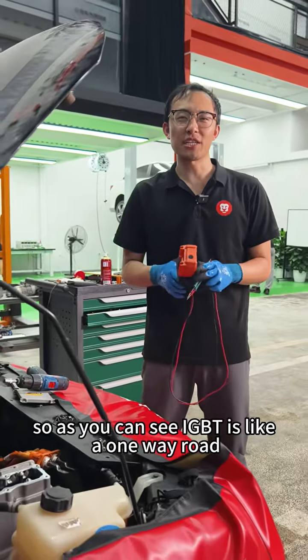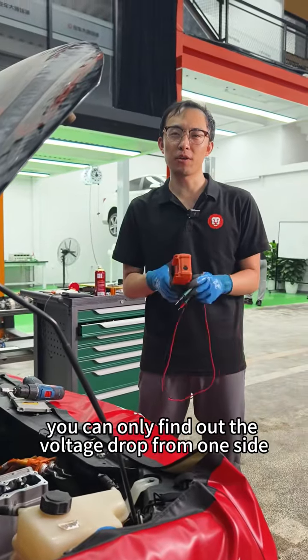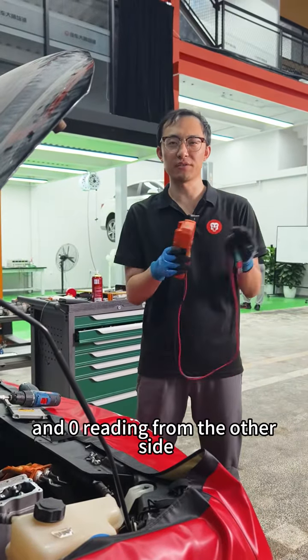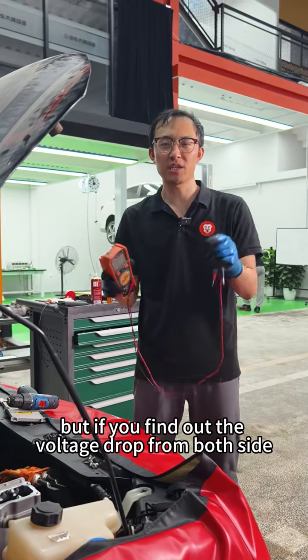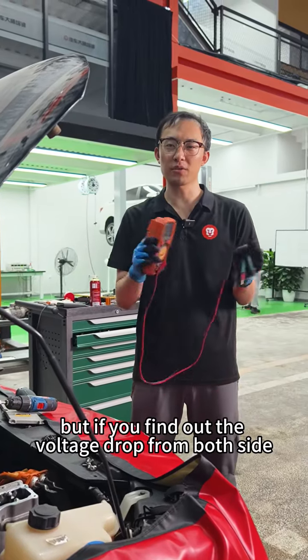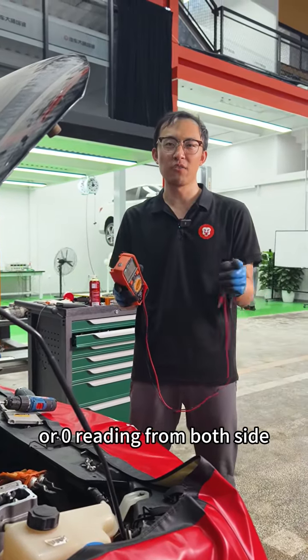So as you can see, IGBT is like a one-way road. You can only find out the voltage drop from one side and 0 reading from the other side. But if you find out the voltage drop from both sides or 0 reading from both sides, which means the IGBT has a problem.